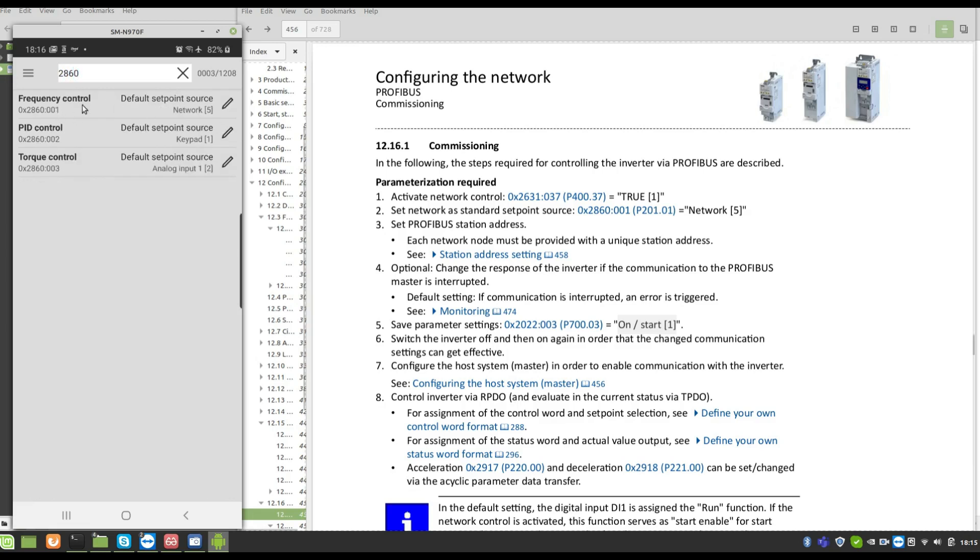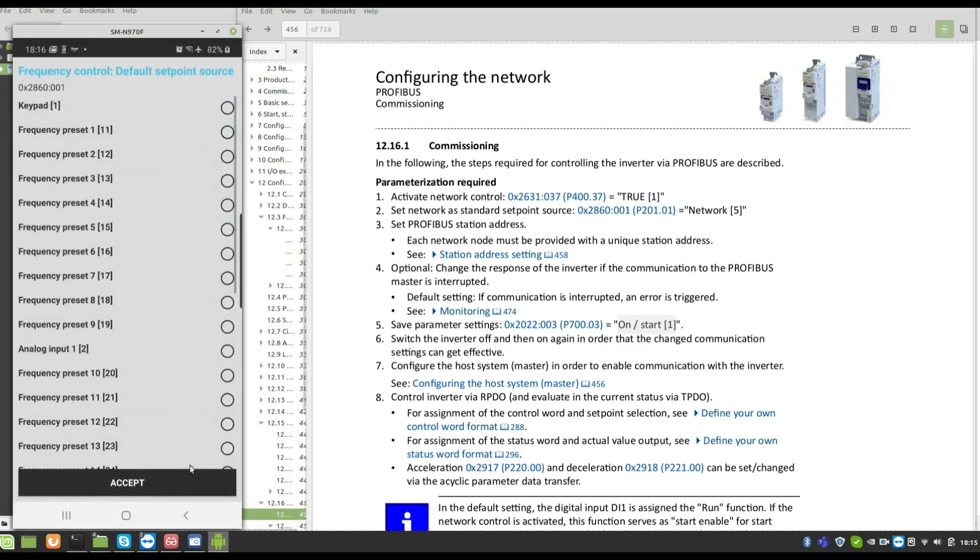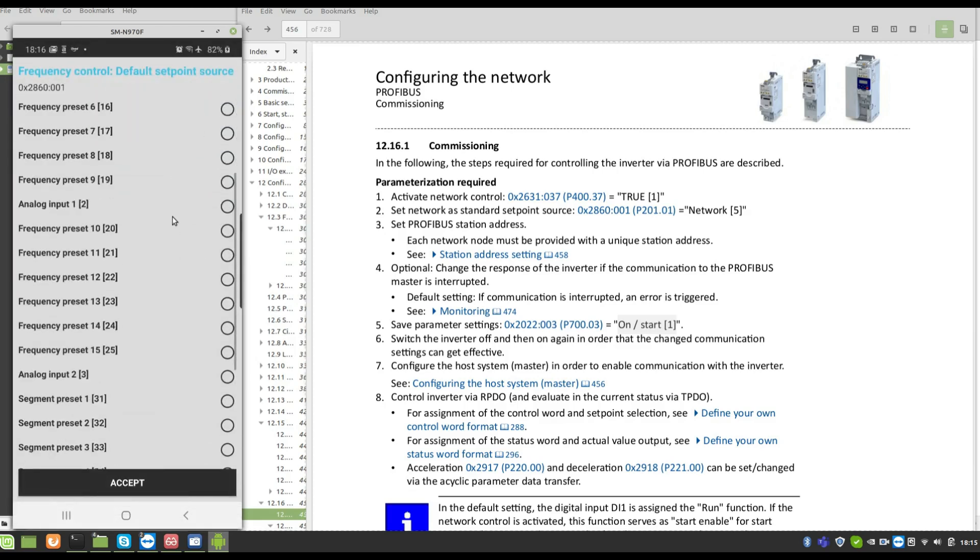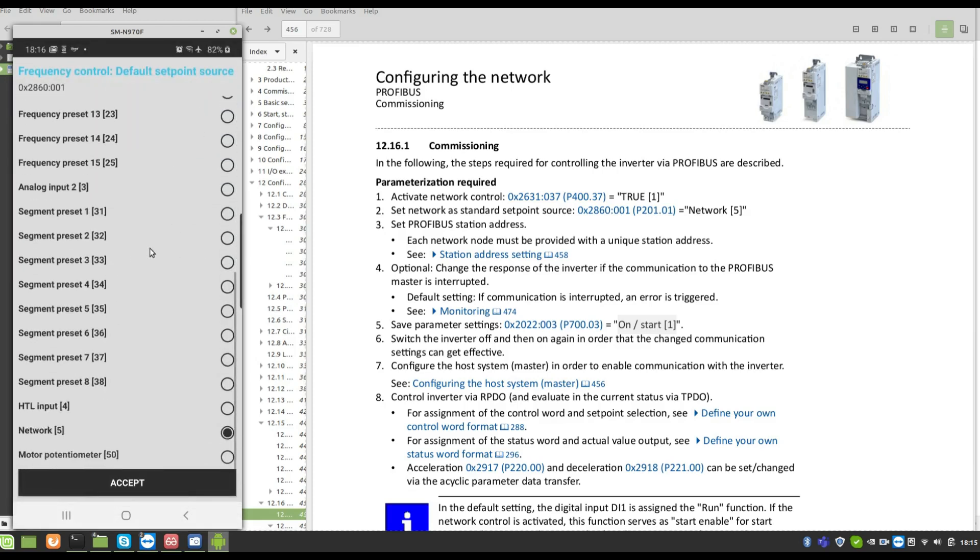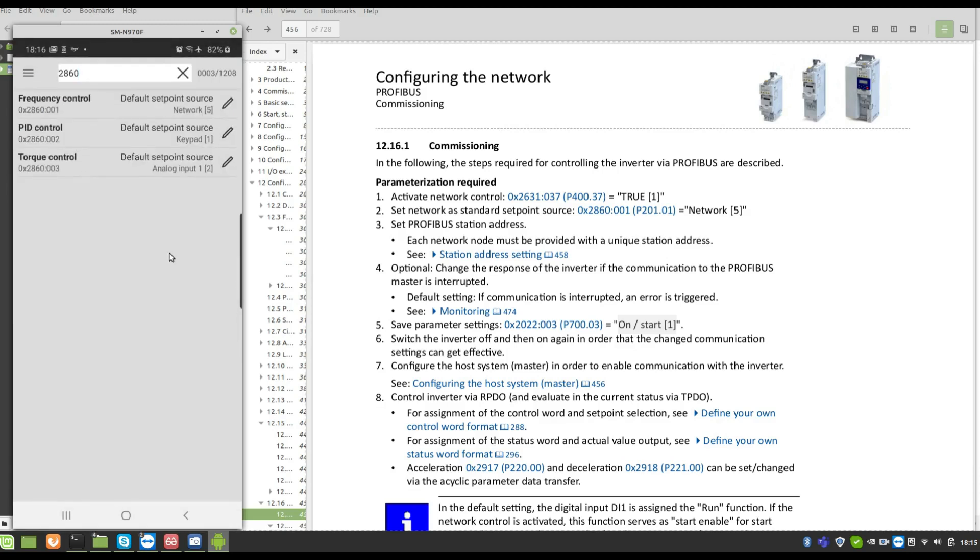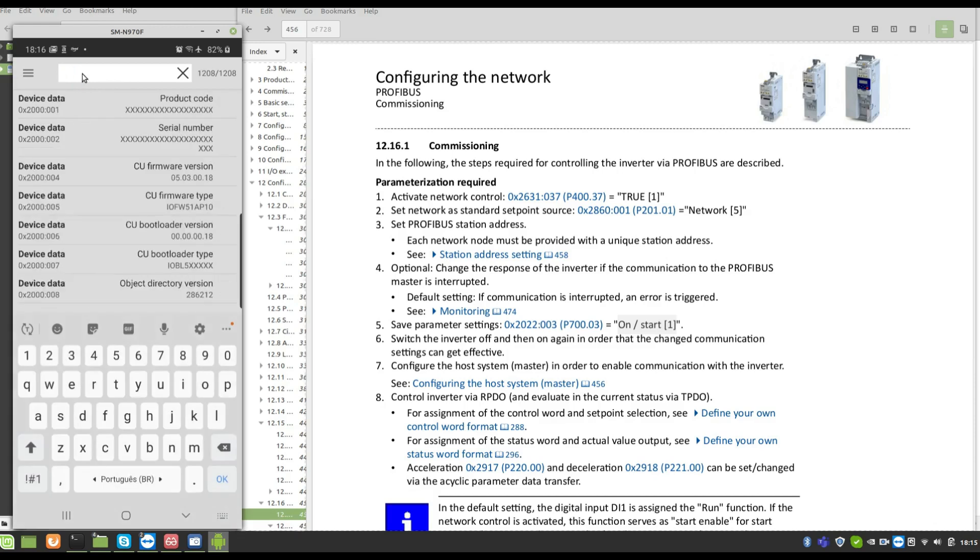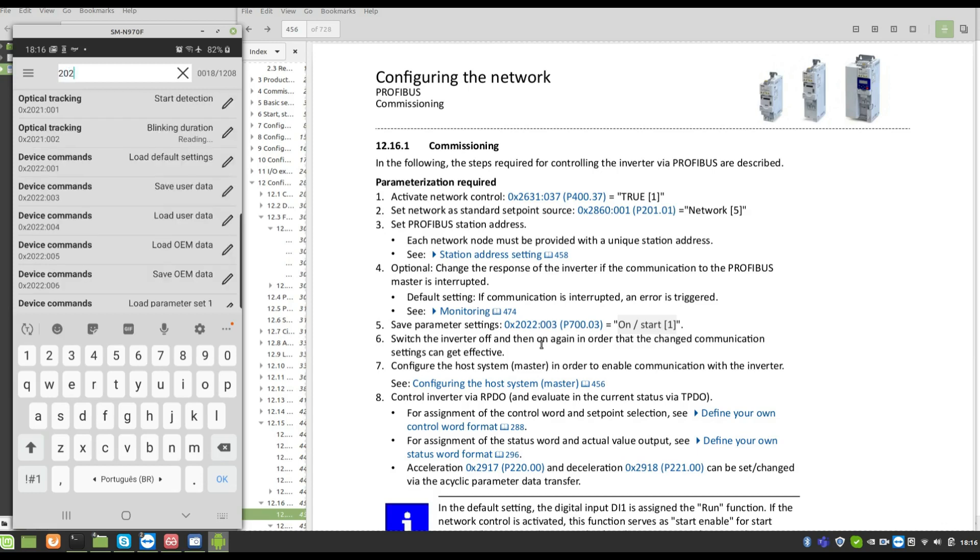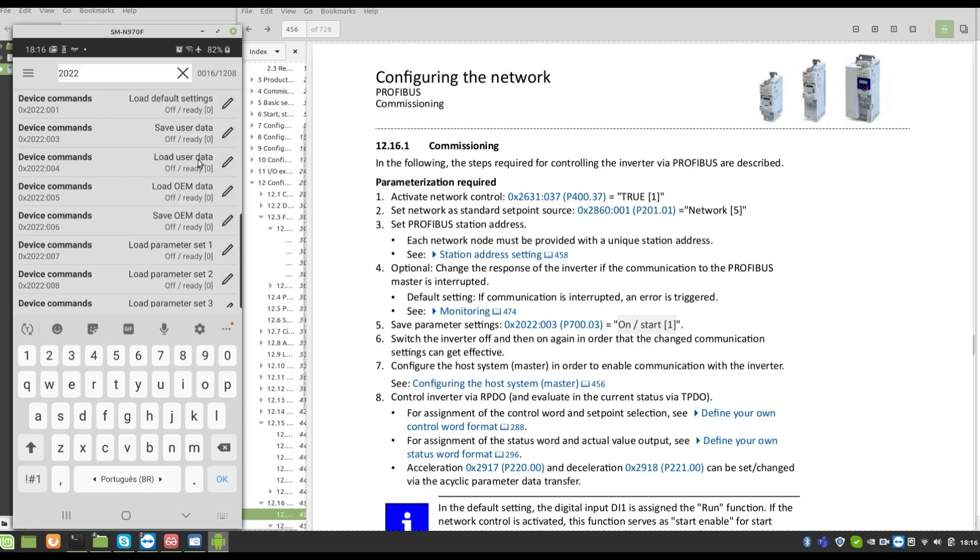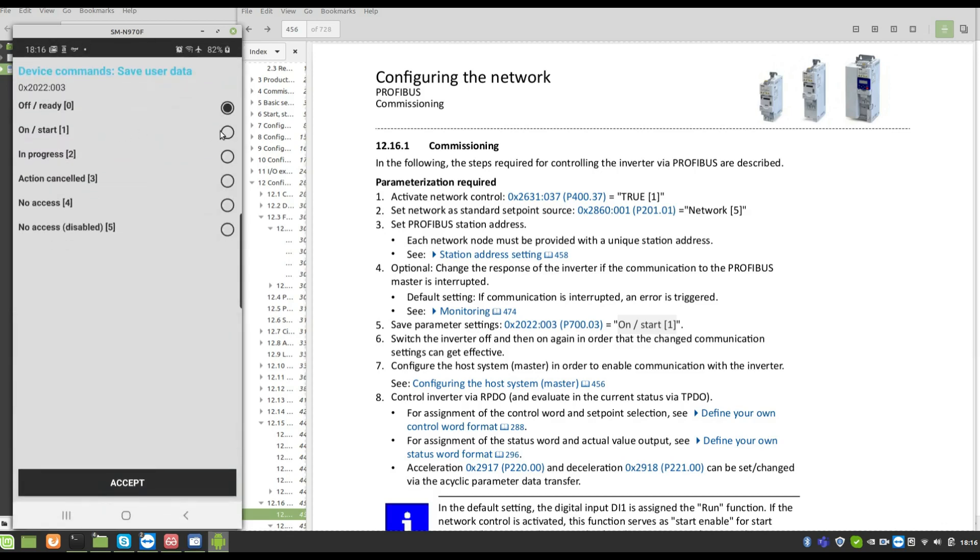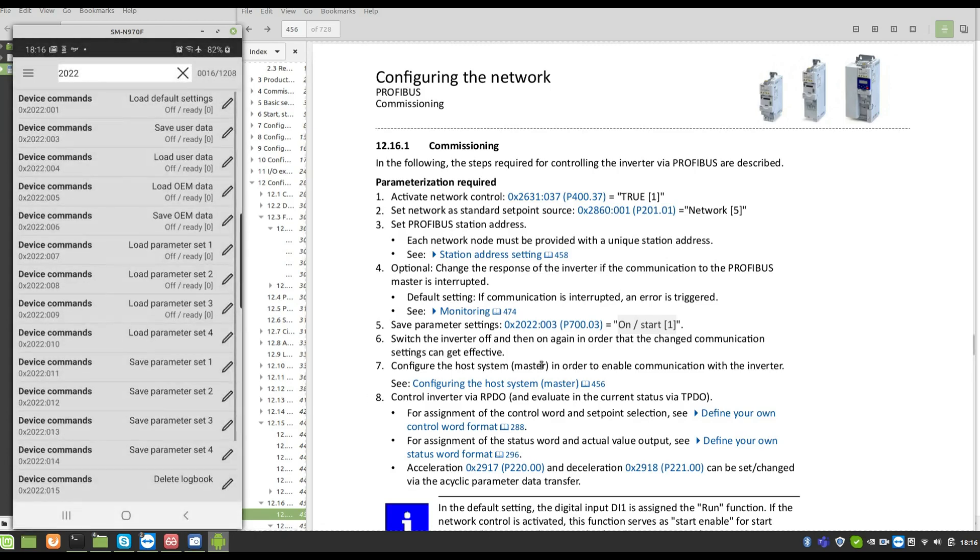2860 sub-index 1, value 5. Must put 5. Look, network, set. Now I just have to save the parameters. P700, save user data, accept.